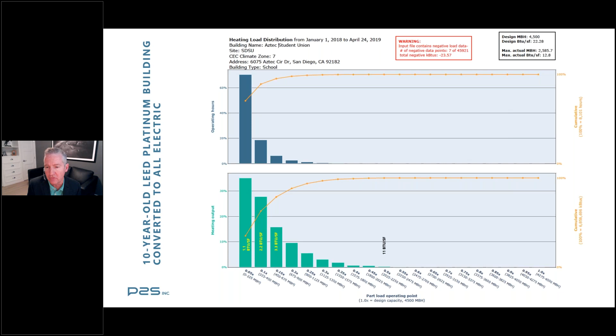On the first bullet, I show the different refrigerants we're currently using today, with what their ambient restrictions normally are. So if you're below 35 degrees, R134A is not going to be a good solution for you. You're going to have to go to R410A. But these are HFC refrigerants, at least the two on the left.